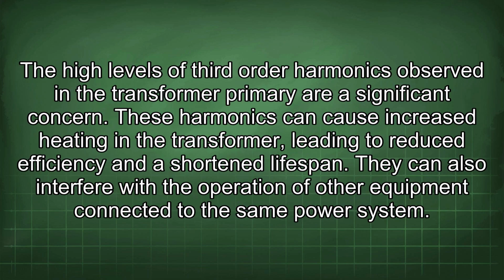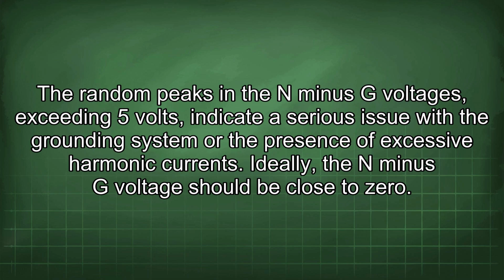The high levels of third-order harmonics observed in the transformer primary are a significant concern. These harmonics can cause increased heating in the transformer, leading to reduced efficiency and a shortened lifespan. They can also interfere with the operation of other equipment connected to the same power system. The random peaks in the N-G voltages exceeding 5 volts indicate a serious issue with the grounding system or the presence of excessive harmonic currents.